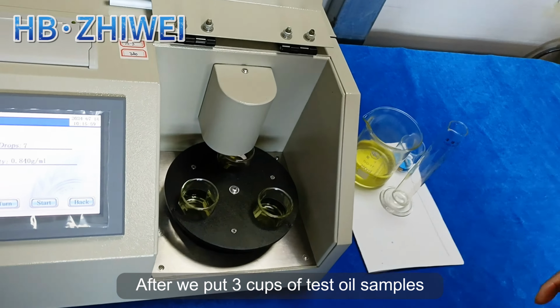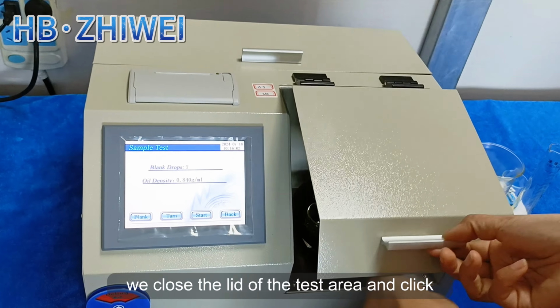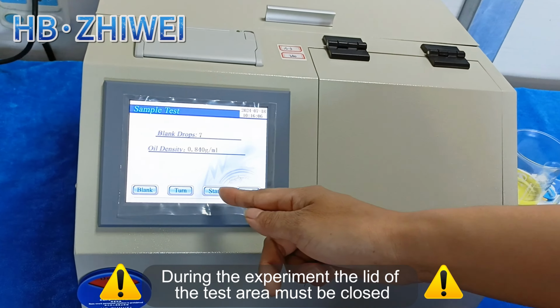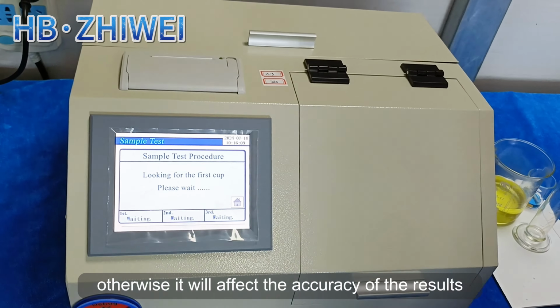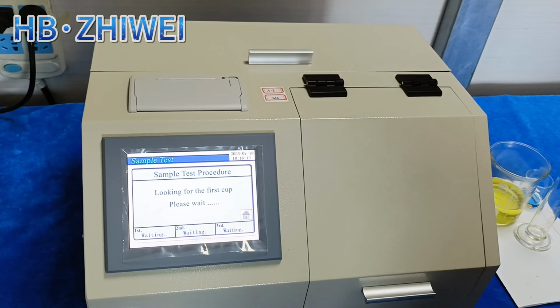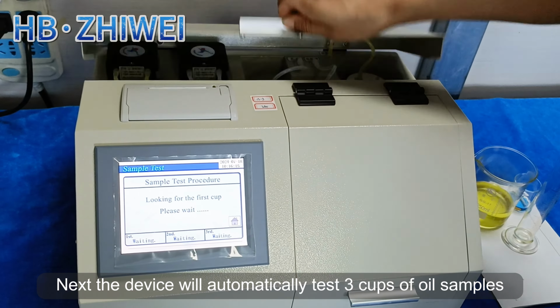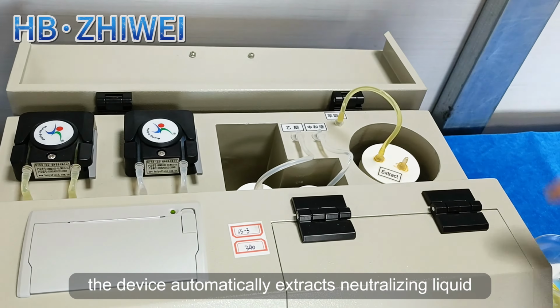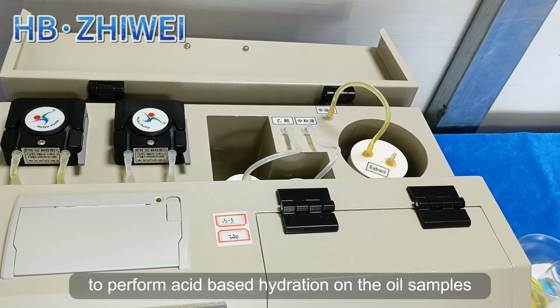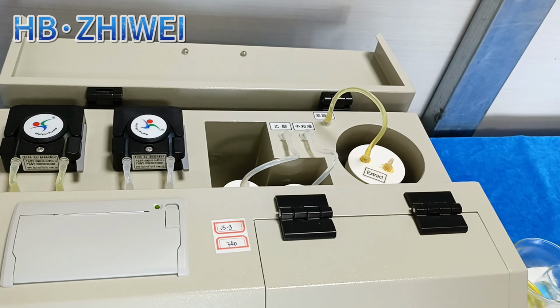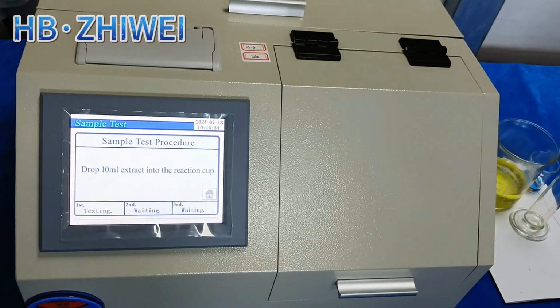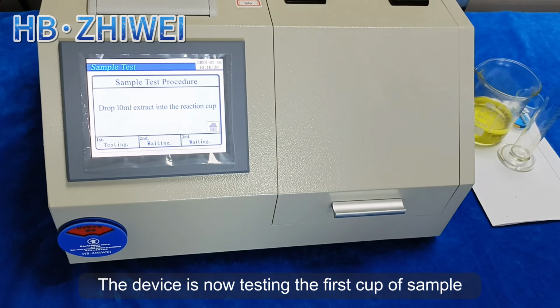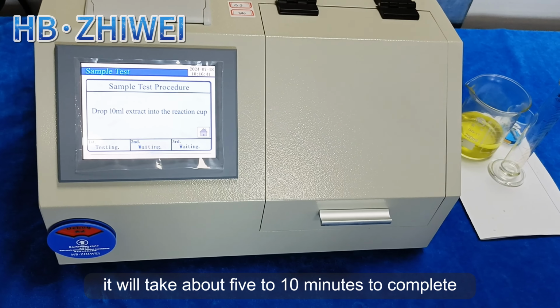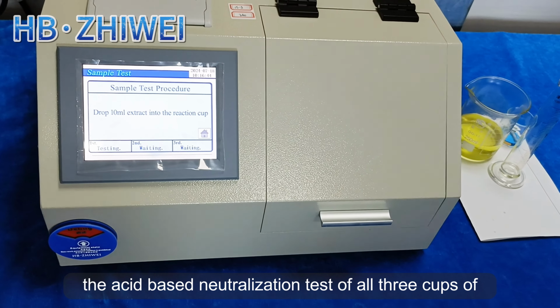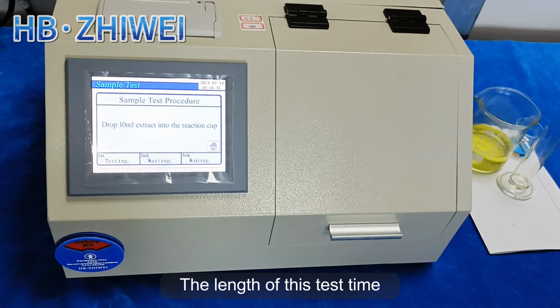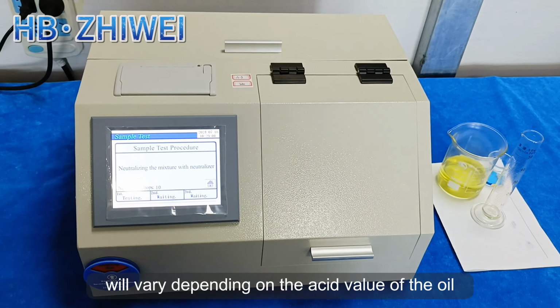After we put 3 cups of test oil samples, we close the lid of the test area and click Start to start the test. During the experiment, the lid of the test area must be closed, otherwise it will affect the accuracy of the results. Next, the device will automatically test 3 cups of oil samples. The device automatically extracts neutralizing liquid to perform acid-base titration on the oil samples. The device is now testing the first cup of sample. It will take about 5 to 10 minutes to complete the acid-base neutralization test of all 3 cups of oil. The length of this test time will vary depending on the acid value of the oil.